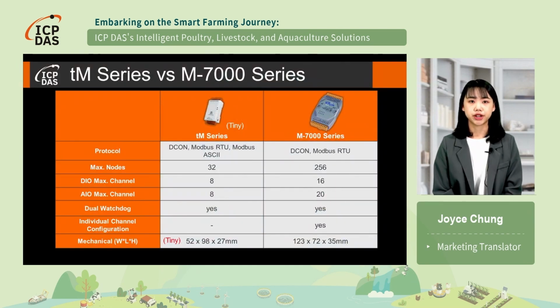Now, let's quickly compare the TM series Tiny I/O modules and the M7000 series I/O modules. Beyond their size difference, these modules offer distinct features as follows. Starting with communication protocols, the TM series support DCON, Modbus RTU, and Modbus ASCII, while the M7000 series accept DCON and Modbus RTU protocols. In terms of scalability, the TM series accommodates up to a maximum of 32 nodes. On the other hand, the M7000 series surpasses this with a capacity for up to 256 nodes, providing a more extensive network reach.